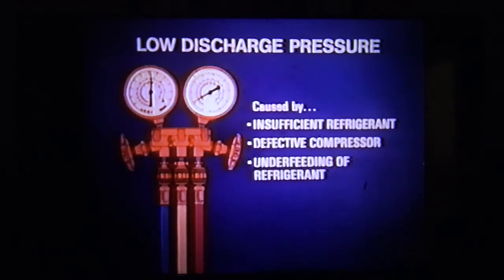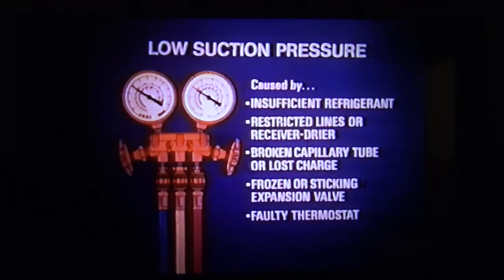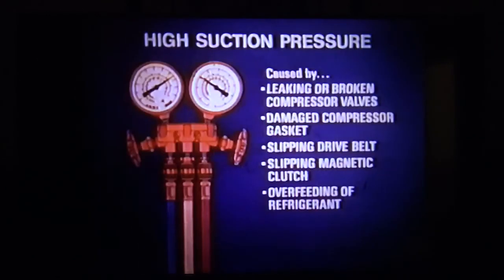Low discharge pressures may indicate insufficient refrigerant, a defective compressor, or underfeeding of refrigerant by the expansion valve caused by a valve blocked by ice or dirt or by a defective feeler bulb. Low suction pressure may be caused by insufficient refrigerant, a restriction in the lines or receiver dryer, a broken expansion valve capillary tube or lost charge, a frozen or sticking expansion valve, or a faulty thermostat.